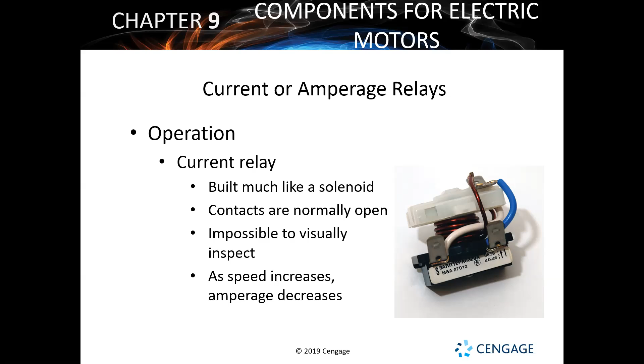Again, current relays, most are easy to troubleshoot. You just basically make sure that it's opening and closing. With most relays, that's what you're going to be looking to do. You've got to make sure that they are allowing power to pass through when they're supposed to, and they're stopping power from passing through when they're supposed to. Basically, how are they operating? Is the switch opening and closing? Because that's what a relay is. At the end of the day, a relay is simply a modified, sophisticated switch.